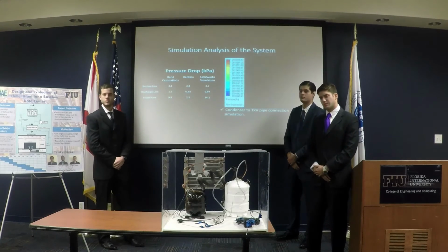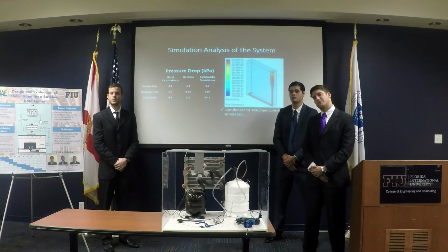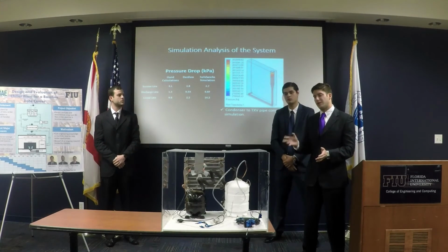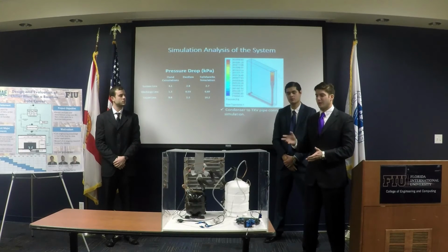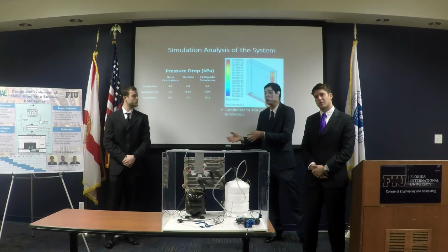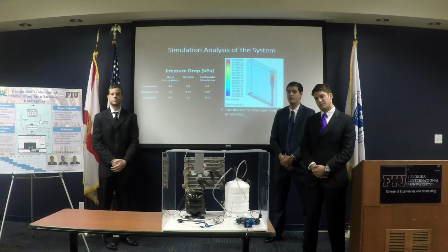Okay, thank you. And then my very last question for you is, in your life cost analysis, did you account for maintenance? No, we didn't. We didn't account for it because we think that from the manufacturer it's going to be the same cost. That's why we didn't put them different. We're assuming the maintenance for our chiller manufacturers is going to be similar numbers. So the main differentiating factor was the energy consumption based on the efficiencies.